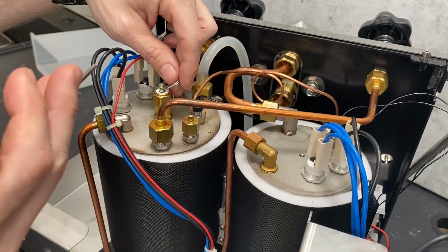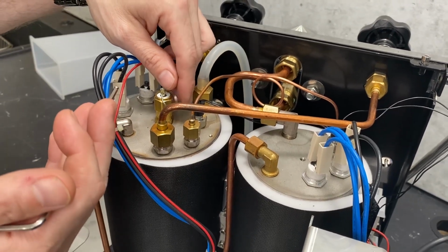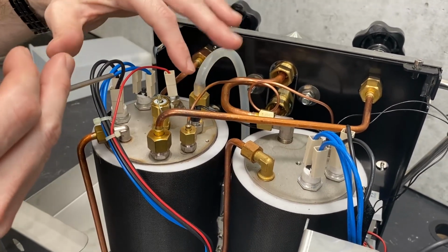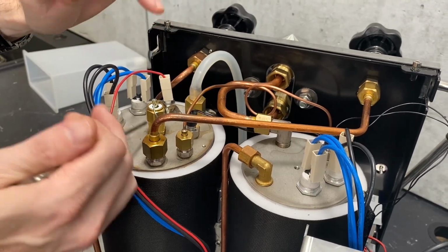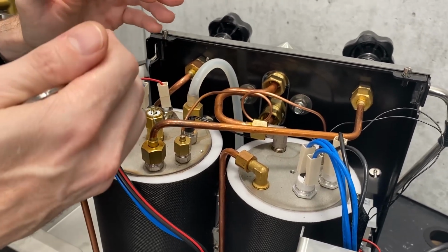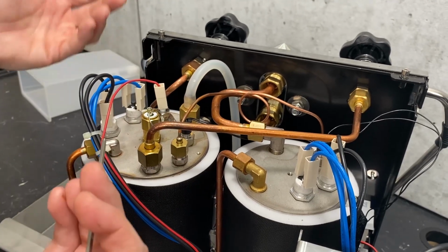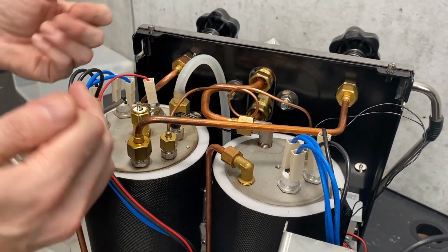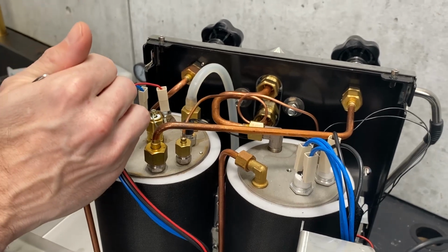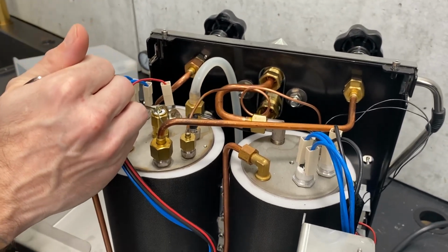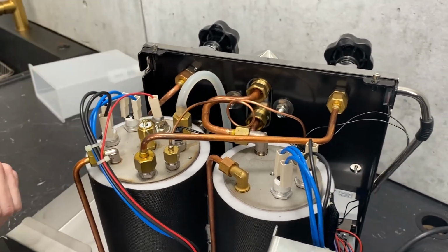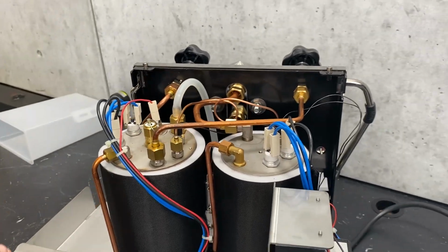But I have noticed in my experience that they tend to be a little bit weaker, and they'll start to hiss a little bit at a lower temperature after they've blown off, especially if it's an older machine with some scale in there. We never, ever recommend rebuilding these, so if you're ever having an issue with it, just replace it. Safety first.